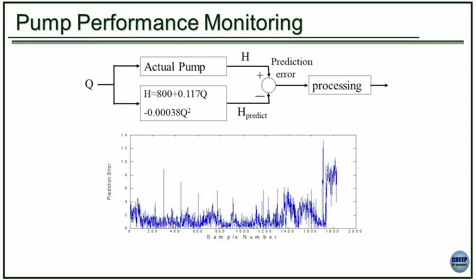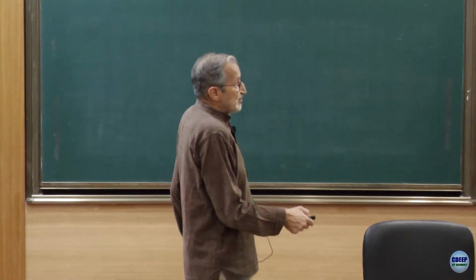We feed in the flow rate Q, measure the actual head, and compare it with the predicted head. Again, data analysis is important: you look at the error. Flow sensors are very noisy. A simple air bubble in a differential pressure cell causes havoc, becoming a very noisy measurement.